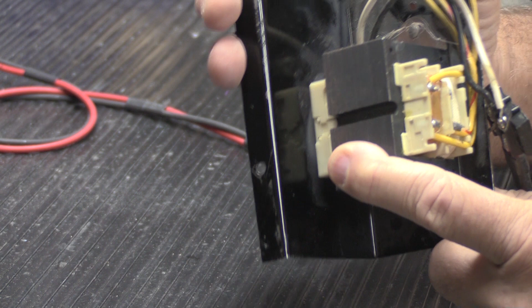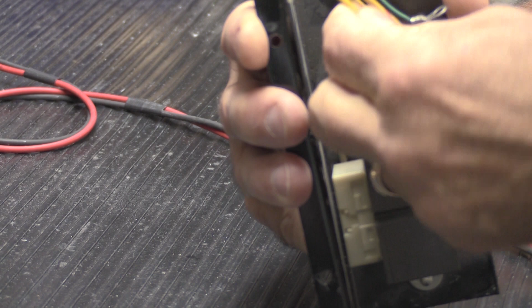You might be thinking, what's a center tap transformer? It's a standard class 2 low voltage transformer that has 3 output wires. Most people are familiar with transformers that have 2 screws on them, but some transformers have a 3rd tap. They can actually have more than that - you can have multi-tap transformers. I've seen transformers with as many as 6 different taps. Different taps mean you get different voltages from different parts of a single transformer.